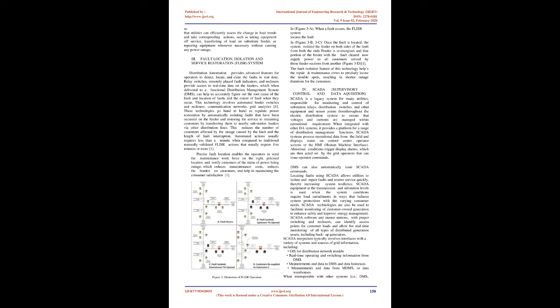3. Fault location, isolation, and service restoration, FLISR, system. Distribution automation provides advanced features for operators to detect, locate, and clear the faults in real time. Relay switches, remotely placed fault indicators, and reclosers provide access to real-time data on the feeders, which when delivered to a functional distribution management system, DMS, can help accurately figure out the root cause of the fault, the location of faults, and the extent of the fault when they occur.